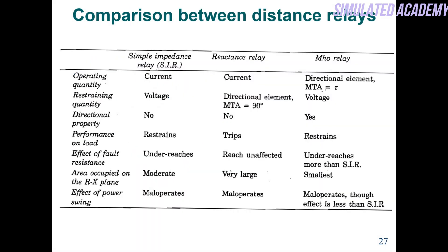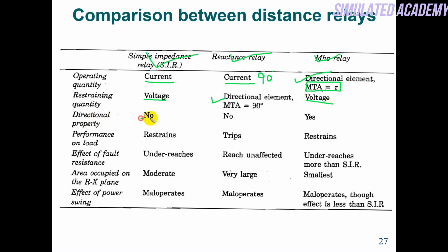So that is how you will use the Mho relay. This is a comparison table we discussed earlier for three different types of relay: simple impedance relay, reactance relay, and Mho relay. Let's summarize: operating quantities — current is involved in all three. For the Mho relay, the directional element with angle τ is the operating component. For the reactance relay, 90 degrees was maintained. Restraining quantities: voltage for simple impedance and Mho relay, while MTA for reactance relay. Directionality property is present in the Mho relay but not in reactance or simple impedance relay.